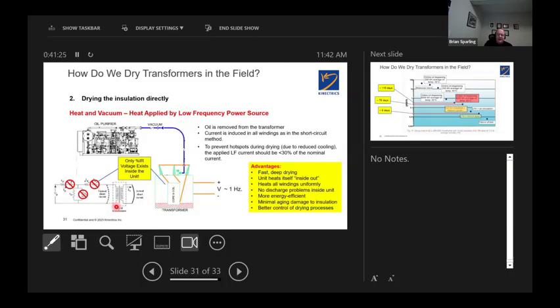With low frequency heating, this technique has been around for at least 12 or 15 years. It's been commonly used in Europe and in some places here in North America. It's basically a combination of heat and vacuum. And again, the transformer has to be able to sustain vacuum. And the difference here is that there's a power supply that we apply to the transformer, and you short out the primary side, apply current to the low voltage side, and at a frequency of 1 hertz, not 60, 1 hertz. That way, from a dielectric perspective, you're not going to hurt anything inside the transformer, but you will certainly be heating up all of the windings.